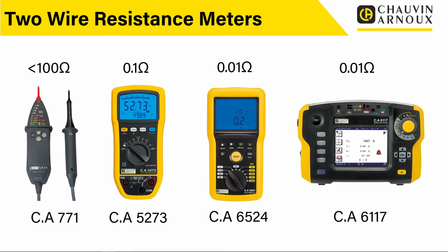Those testers, when you look at the accuracy at the very low values with the 2-wire test, are quite limited in their accuracy, and quite limited in the information you're actually being told, because it is a 2-wire test. And I'm not just saying this is anything to do with Chauvin Arnoux products, this is just in general. There is a general discussion about whether these types of instruments are really going into the level of continuity that would be useful for electrical installation inspection and testing. Because if we could get to another level of accuracy, we could identify more poor connections, circuit breakers that were starting to wear out, poor bonding connections, all these sorts of things.